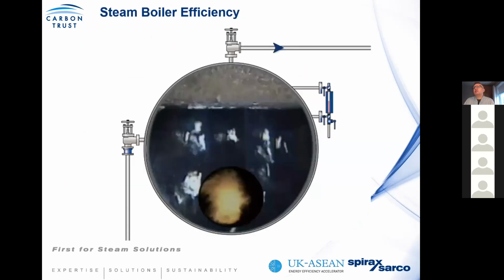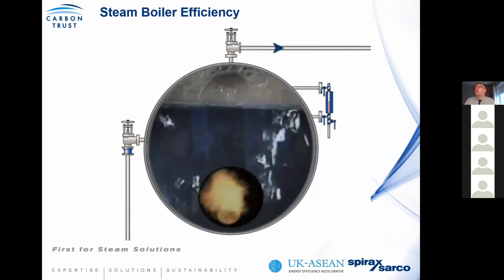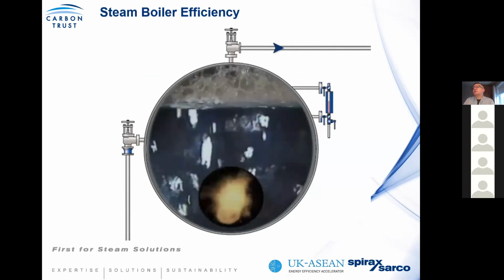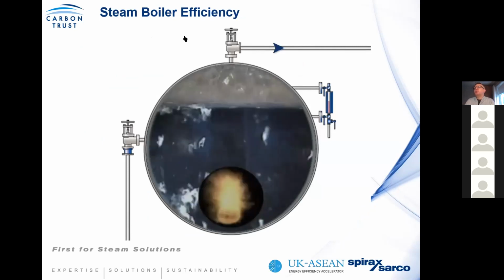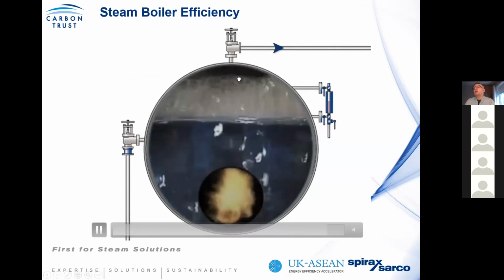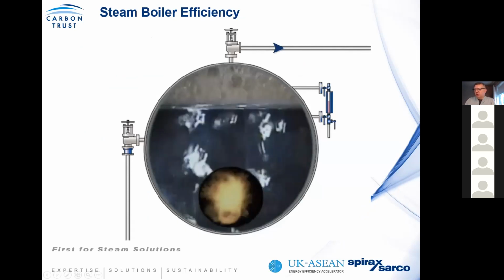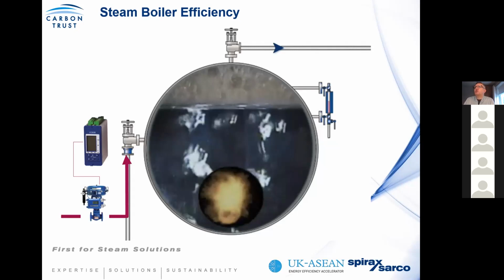Now, this video here gives some insight into the boiler. What you're seeing is that the steam space, or the disengaging space, is this region above the water. Depending on how the system operates will determine whether you have a very turbulent system or not. And again, the pressure will determine the foam content around the surface of the water. What's important to try and control this is that we should be looking at the mode of boiler level control. Because if you employ on-off control, or if you find that your modulation control is acting in an on-off condition, each time you add cold water to the boiler, you have the effect of rapidly cooling the boiler.